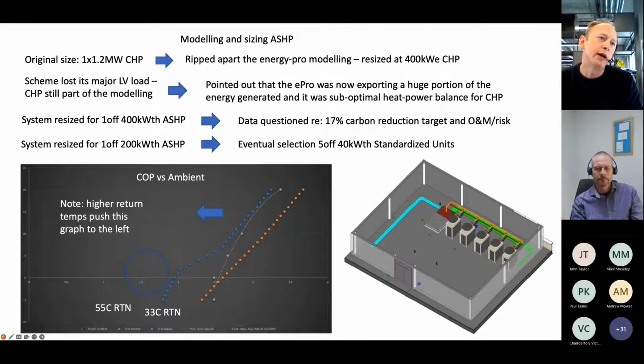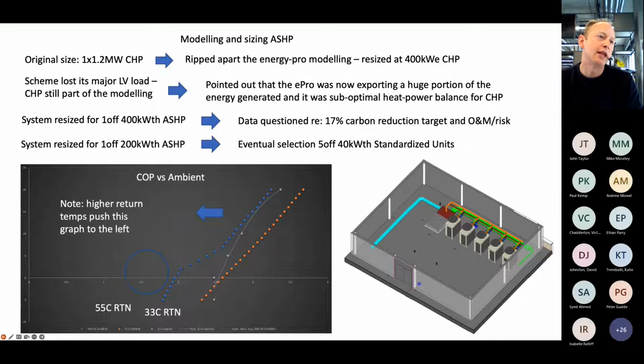We discovered, or we well delved into it, that the large 200 kilowatt units that were being proposed actually didn't have this orange dotted line in terms of COP. They actually had a COP that was more akin to this grey line, which meant that it was very, very close, in fact, extremely close to these smaller units that we were proposing. They still said that it's better, and therefore you should go for the larger units. The issue being is that they don't live the realities of having reliance on one large unit as opposed to 5 smaller units. So we pointed out that the dynamics really can change when you compare apples with apples.